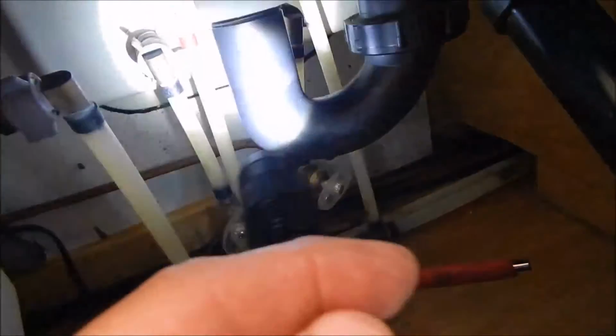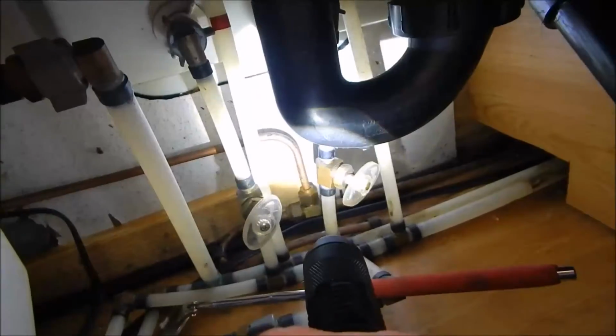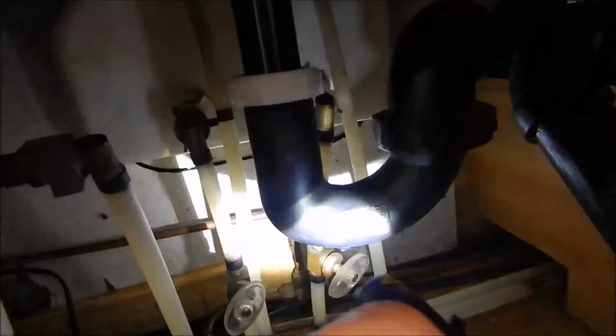Which luckily I did come in here and look at it, because I noticed when it was under pressure and hot water was on, I found a water leak, and it was that old guy right there that was loose. I tightened him up, fixed that. Because it's been bone dry in here. I've been checking it. So I think I got that set at around 115. Between 90 and 120, so I don't have it set real high. And that's the back of the tank you're looking at. That's the thermostat for the electric water heater.